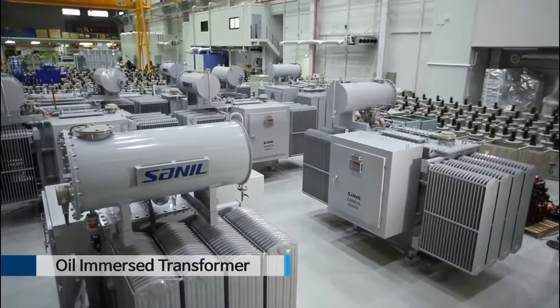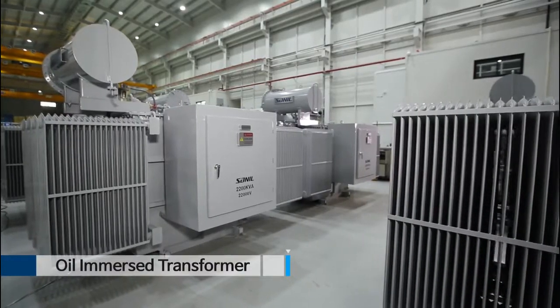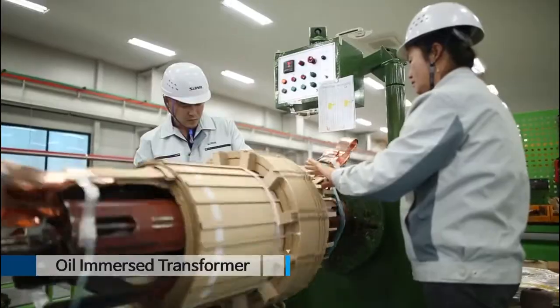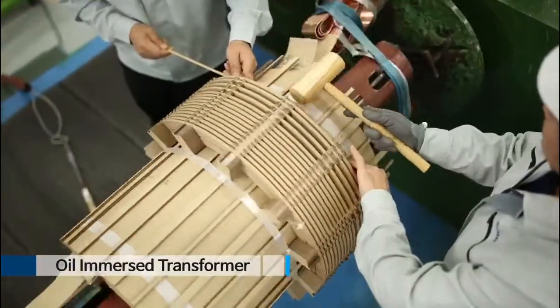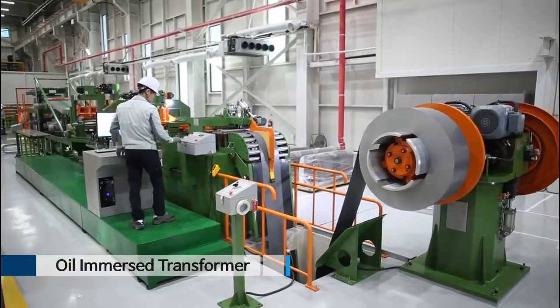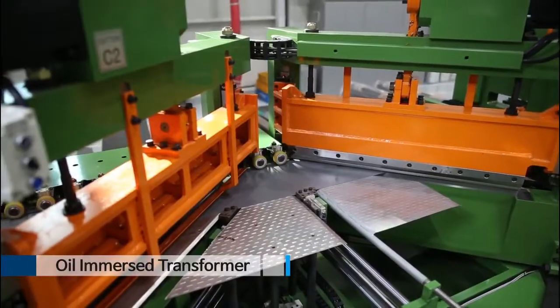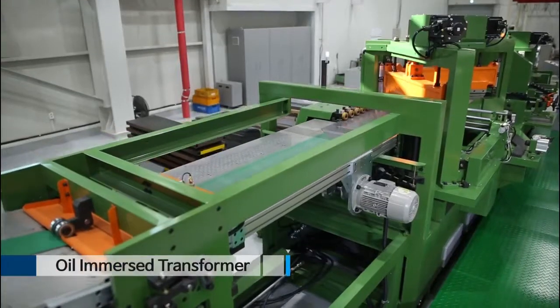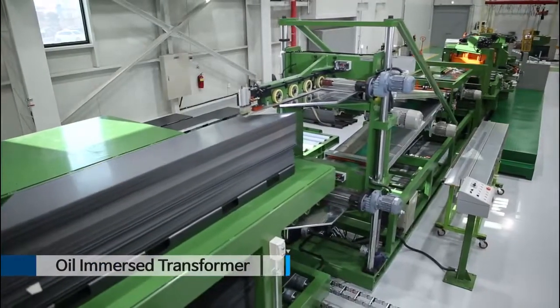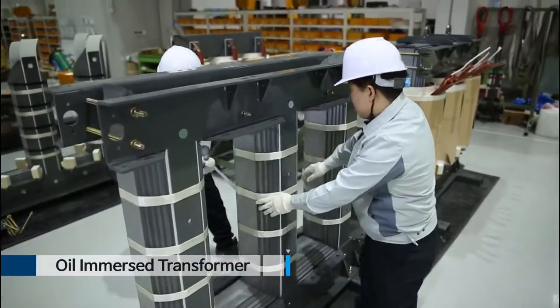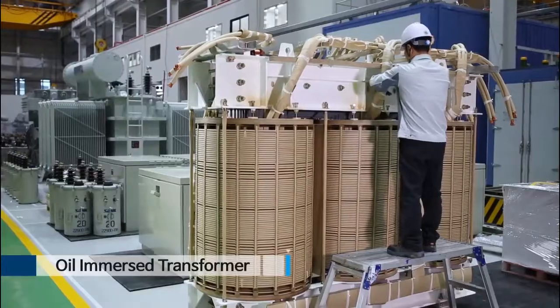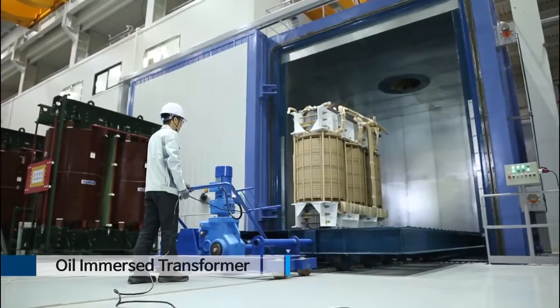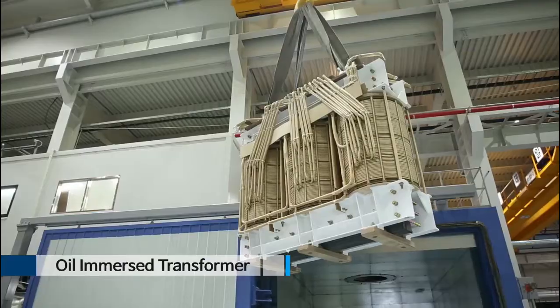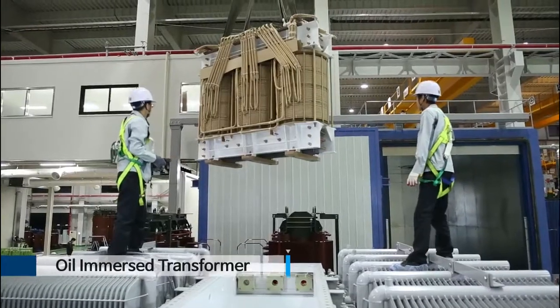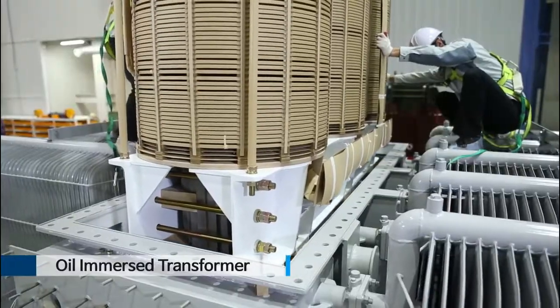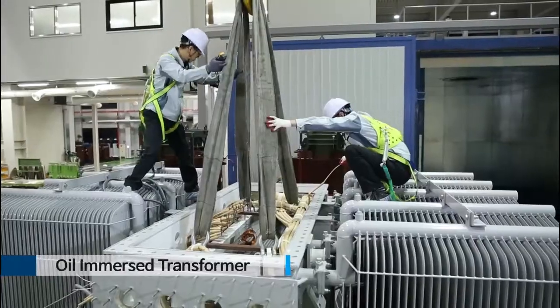The oil immersed transformer is designed to meet the customer's demands. The coil is wound by a qualified technician, and precise core cutting is made by a computer program machine to minimize loss and noise. Assembled cores and coils are moved to a vacuum dry oven to remove the moisture. After sizing according to the design dimensions, they are assembled in the tank and filled with oil filtered by high vacuum oil filtration equipment under vacuum.